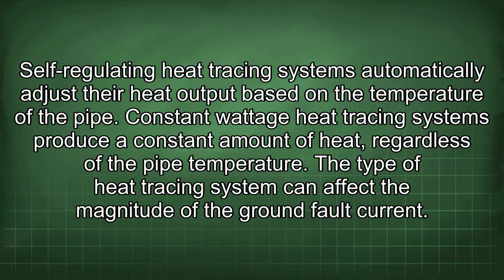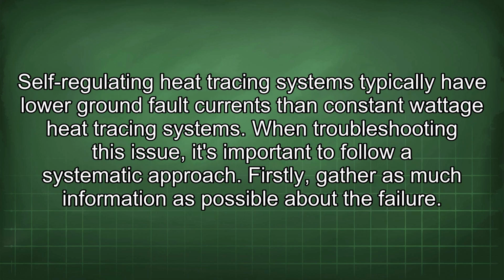Self-regulating heat tracing systems automatically adjust their heat output based on the temperature of the pipe. Constant wattage heat tracing systems produce a constant amount of heat, regardless of the pipe temperature. The type of heat tracing system can affect the magnitude of the ground fault current. Self-regulating heat tracing systems typically have lower ground fault currents than constant wattage heat tracing systems.